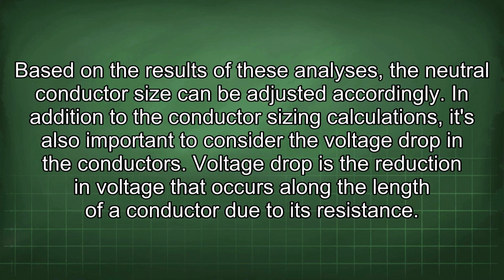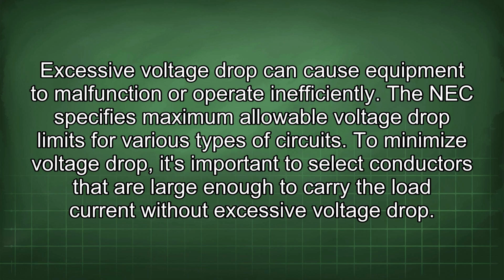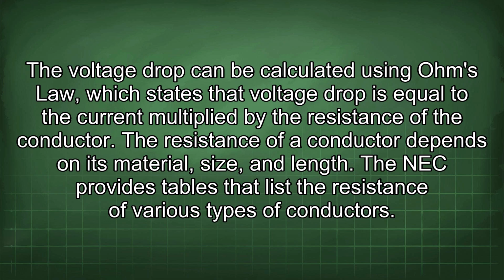In addition to the conductor sizing calculations, it's also important to consider the voltage drop in the conductors. Voltage drop is the reduction in voltage that occurs along the length of a conductor due to its resistance. Excessive voltage drop can cause equipment to malfunction or operate inefficiently. The NEC specifies maximum allowable voltage drop limits for various types of circuits. To minimize voltage drop, it's important to select conductors that are large enough to carry the load current without excessive voltage drop. The voltage drop can be calculated using Ohm's law, which states that voltage drop is equal to the current multiplied by the resistance of the conductor.